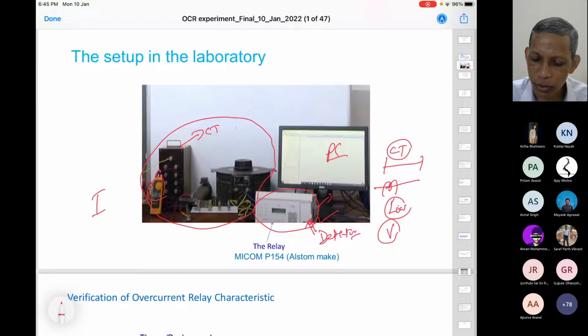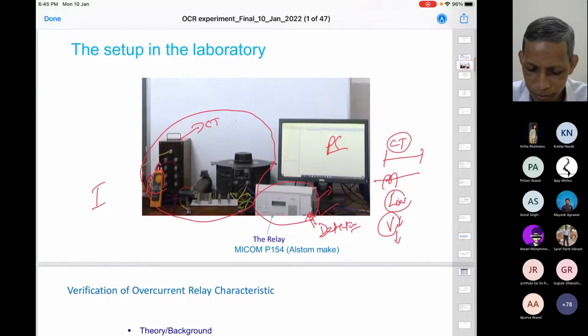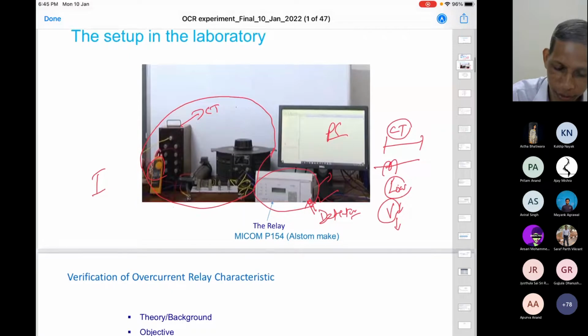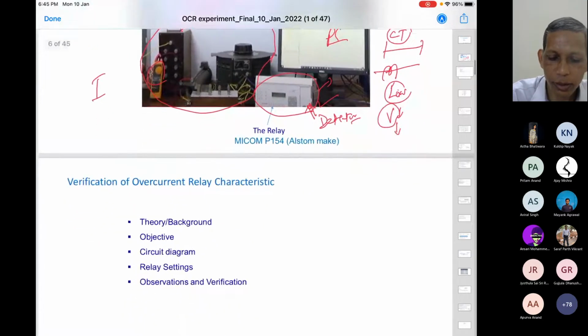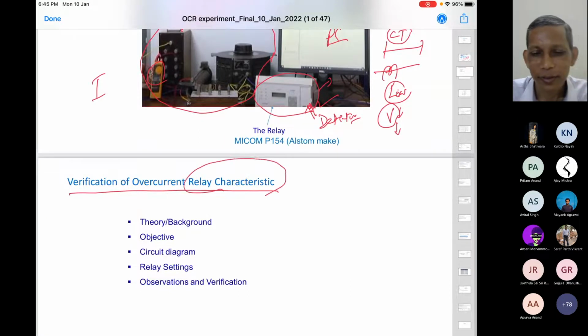The relay does that. And once we have the voltage proportional to the current, this voltage is sampled, processed, digitized, and so on. Okay? That is the process that happens there. So in this arrangement, we have current injection into the particular relay to see whether it's functioning properly or not. What is proper or not, we also try to see. So the purpose is verification of overcurrent relay characteristics. Now, what are relay characteristics? We'll see that. Why do you require characteristics?